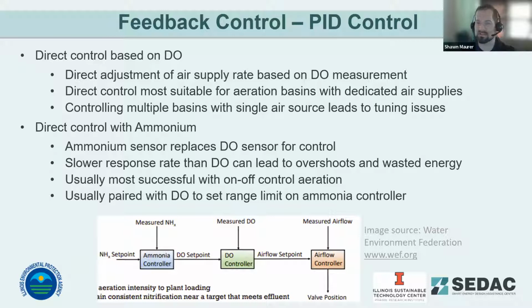An advanced way to do this that we're starting to see is ammonium-based aeration control. So instead of putting a DO sensor in the basin, you've got an ammonium sensor or nitrate sensor in the basin. And a lot of plants are moving towards this because of the increased permit regulations for nitrogen limits in the effluent. The problem with direct feedback control with ammonium is it does have a slower response rate than DO, which can lead to more overshoots and wasted energy. It's generally more successful with on-off aeration control if you're doing a direct feedback control with ammonium.